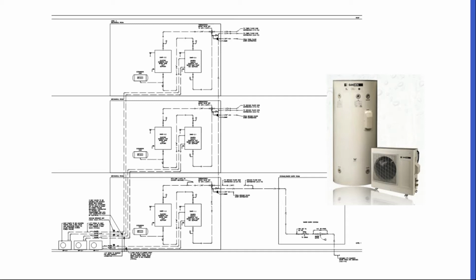So what we did as a backup was an extra tank in each unit. The Sanden tank feeds and separates as it's supposed to, and we had a second storage tank that happened to be an electric resistance tank that was essentially a backup system. Residents never noticed that the Sanden failed.